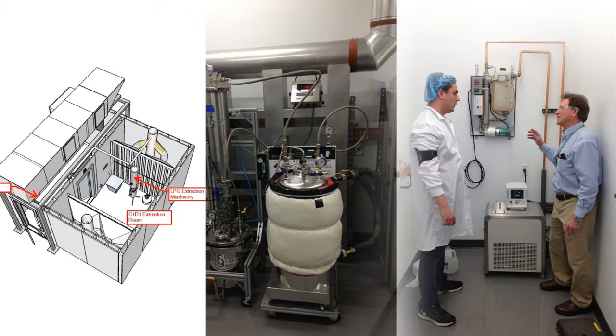There are contractors that do need to participate, though. The kit would still need to be connected to the natural gas of the building and the electrical system in the building. It would still have to have piping or vent ducting for the makeup air and the exhaust air, but all the components would be there. So it's not like there's no installation involved. There is definitely installation involved by electrical contractors and HVAC contractors, but for the most part, it greatly cuts down on the time.